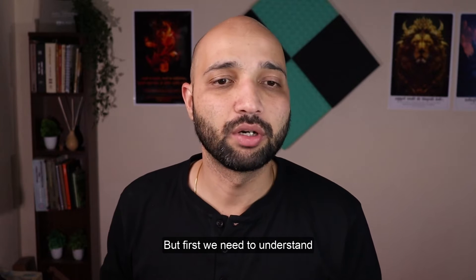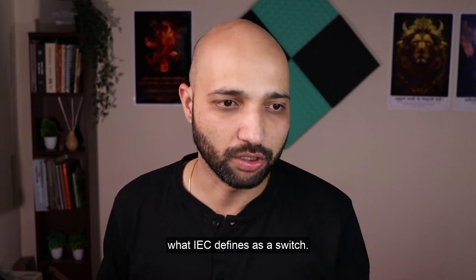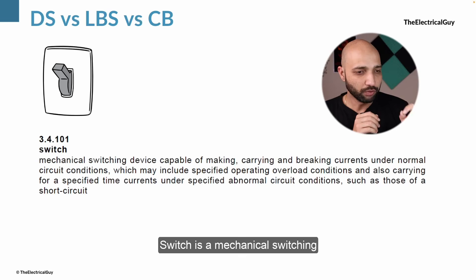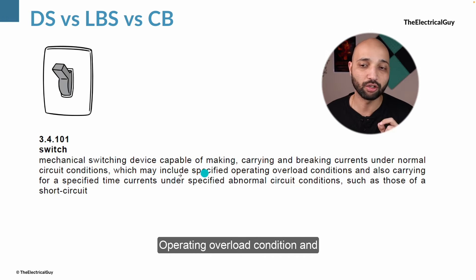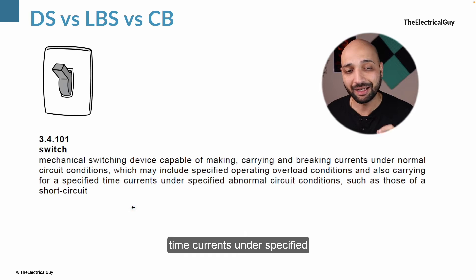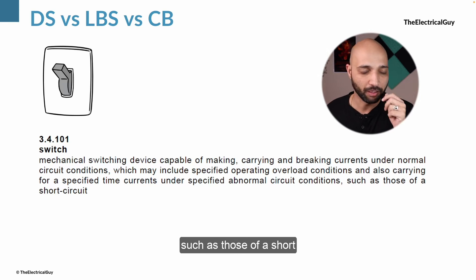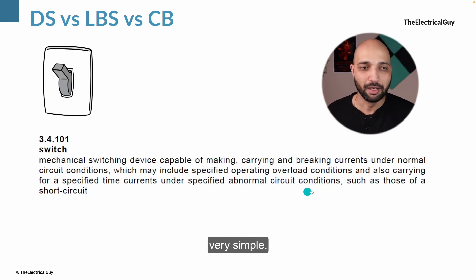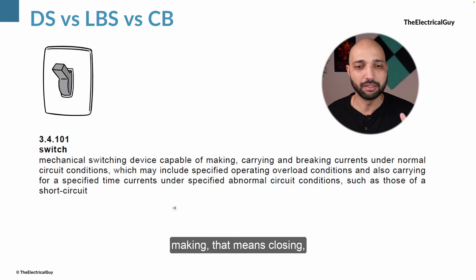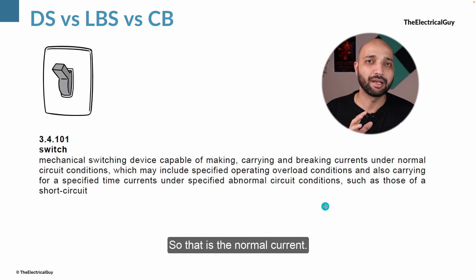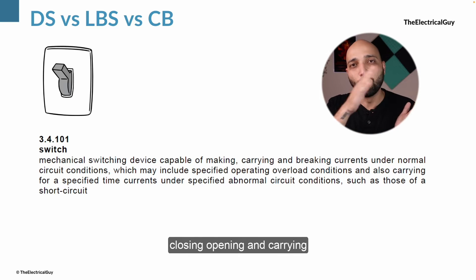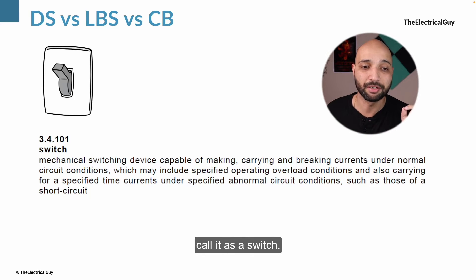First we need to understand what IEC defines as a switch. A switch is a mechanical switching device capable of making, carrying and breaking currents under normal circuit conditions, which may include specified operating overload conditions. So a device capable of closing, carrying and breaking normal currents — for example, if the rated current of your system is 200 ampere, that is the normal current — is what IEC calls a switch.